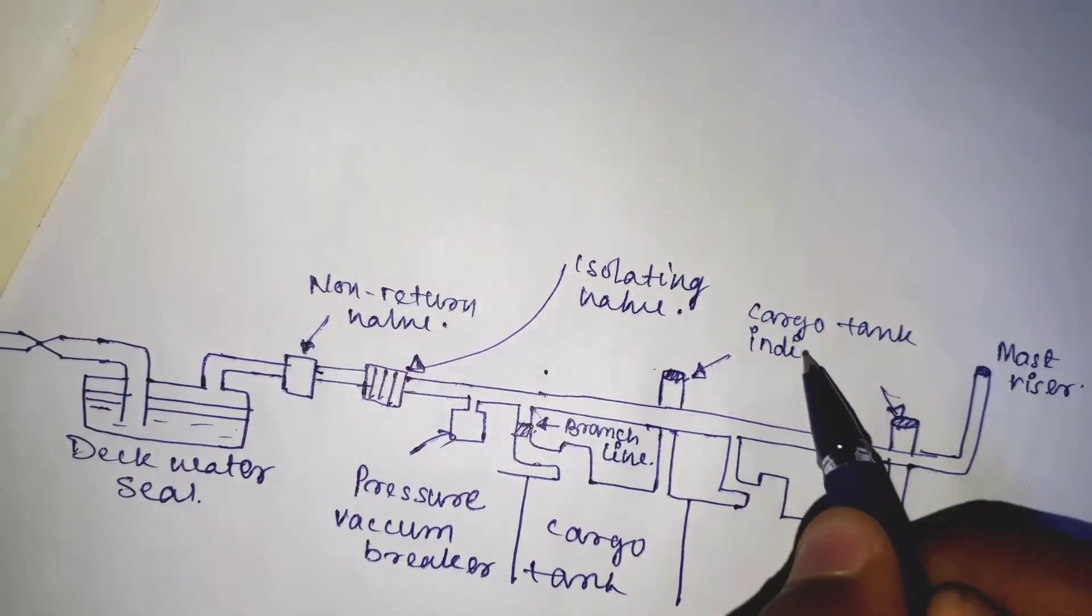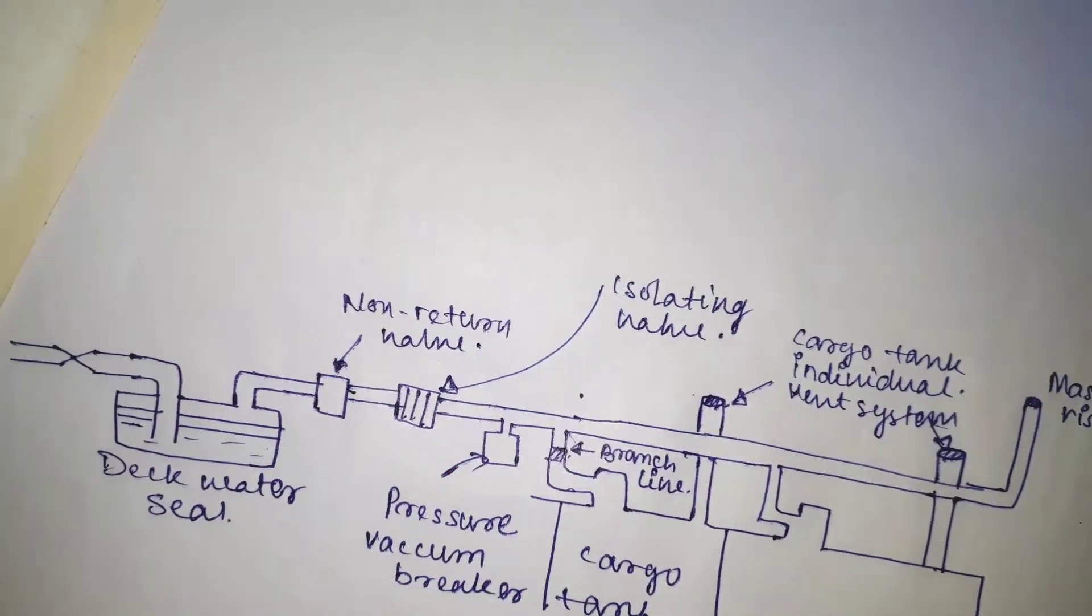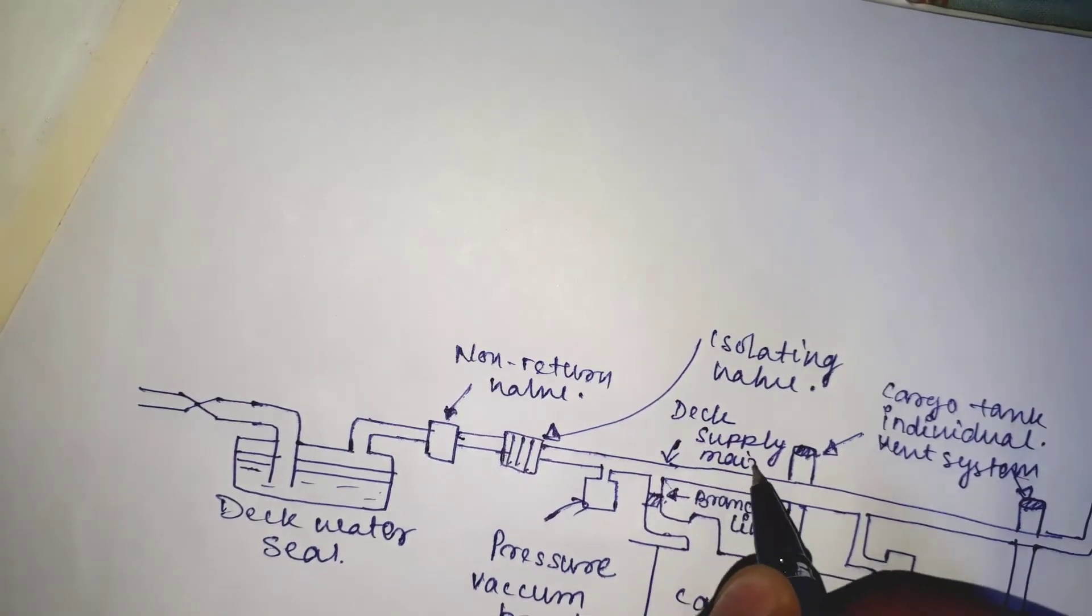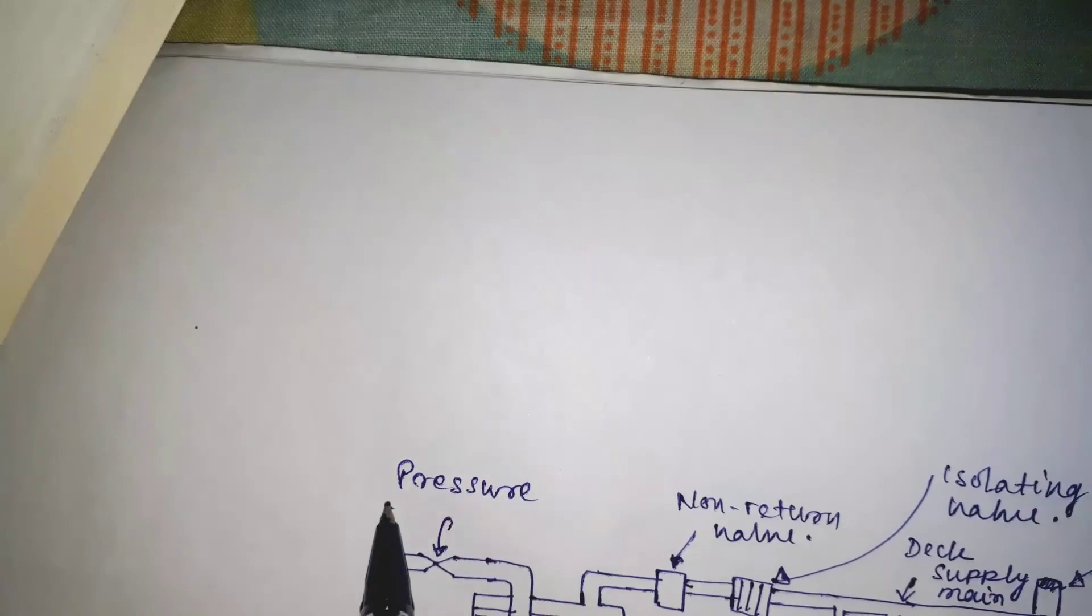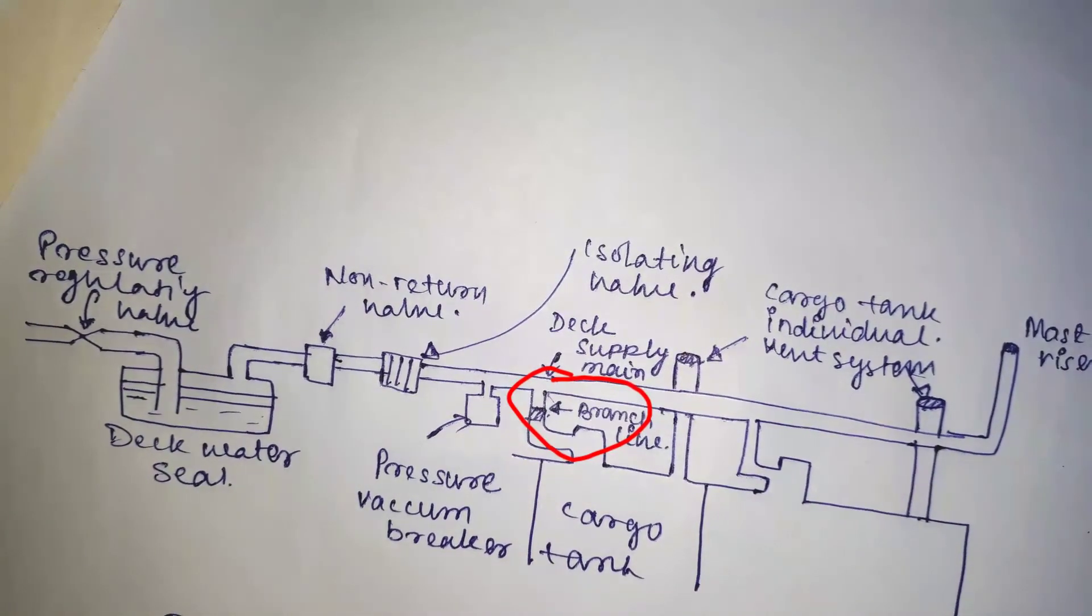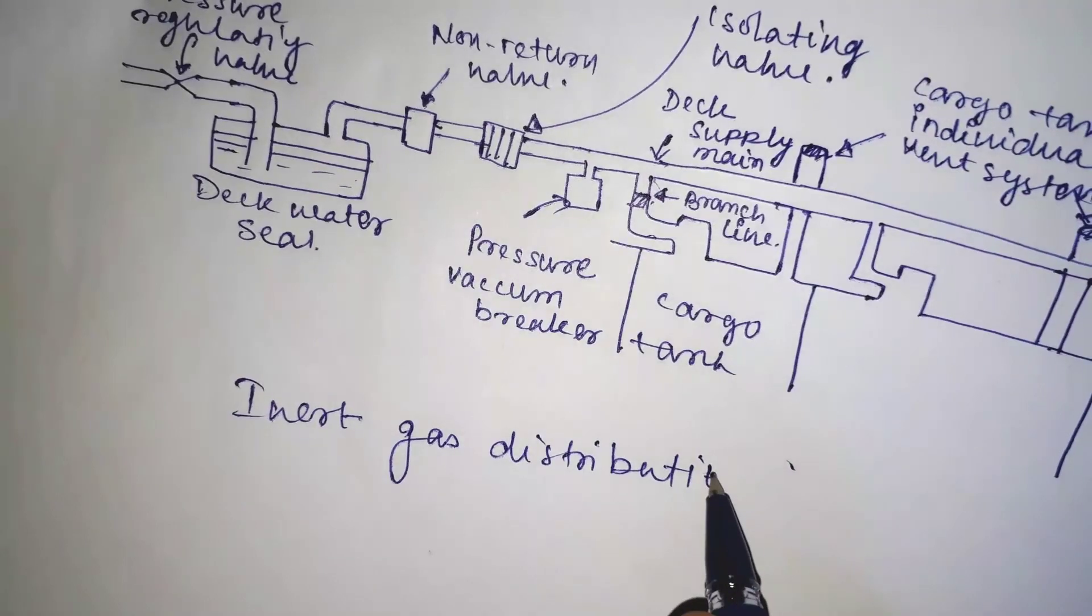The pressure vacuum breakers. These liquid-filled breakers are fitted in the deck gas main to prevent the cargo tanks from being subjected to excess positive pressure and to excess negative pressure. The branch lines. These pipes deliver the inert gas from the deck main to the individual cargo tanks. Another branch line is in the form of a mast riser to allow the venting of the gas to the atmosphere.